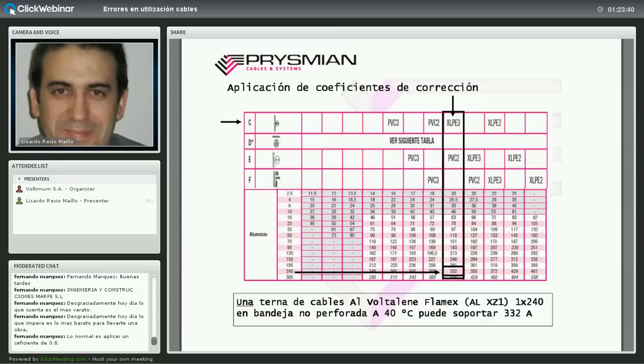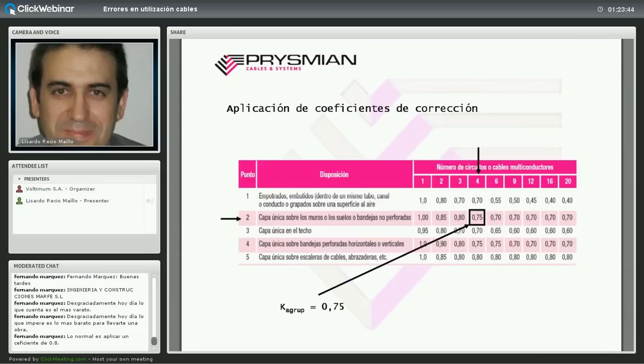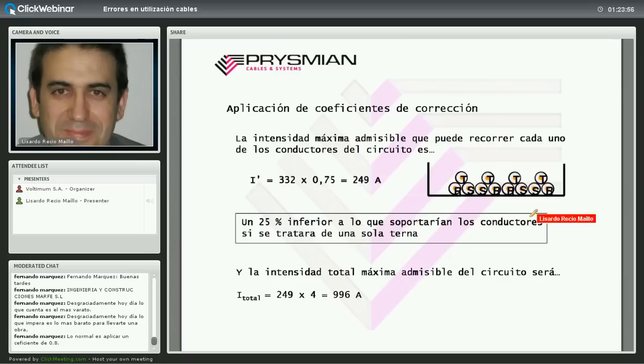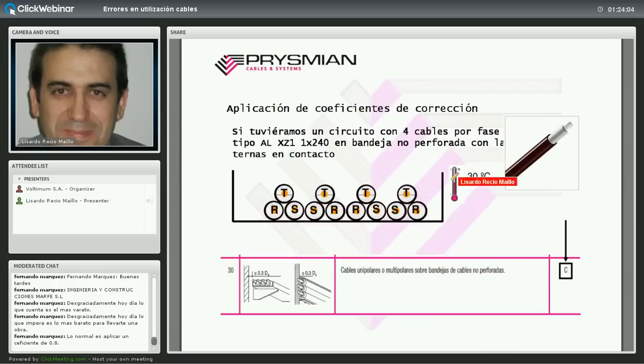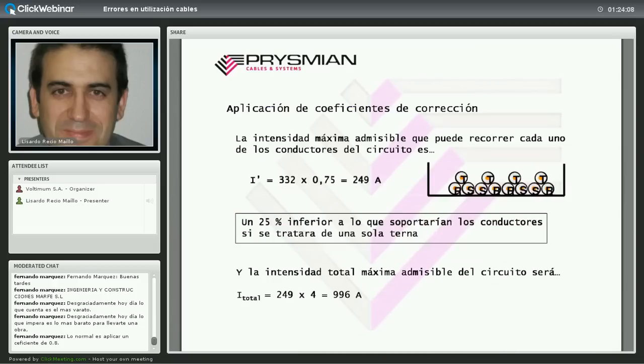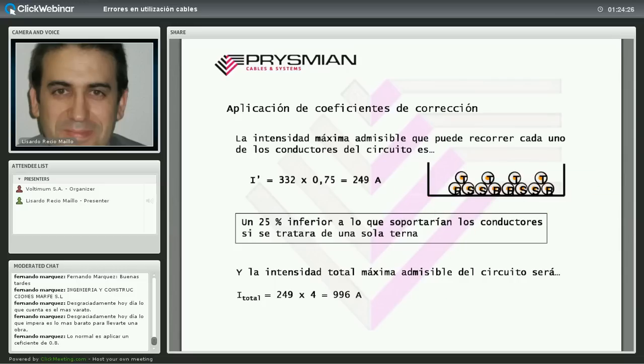Aplicamos el coeficiente de corrección por agrupamiento en capa única sobre bandejas no perforadas: 0,75. Resultado: 332 × 0,75 = 249 A por terna. Como se trata de cuatro ternas, el circuito soporta 996 A en total. Aunque se trate de un mismo circuito con varios conductores por fase, no se exime de aplicar el coeficiente por agrupamiento.